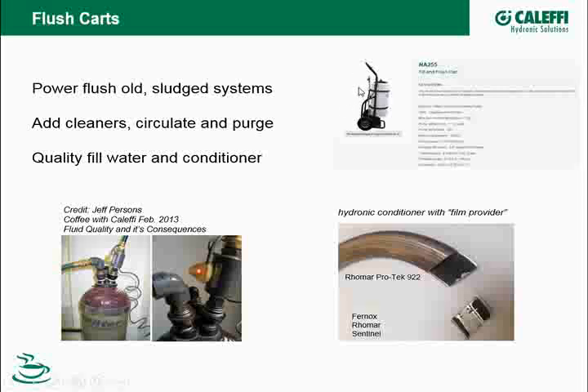Another tool that might be handy is one of these fill and flush carts. Now we build up a bunch of these for guys that were doing solar work. You just dump your glycol here and then you could pump it in there. But it can also be used for purging or cleaning systems. You could put a cleaning compound in here and just run it through there. It's got a pump that'll pump about 80 to 90 pounds pressure, so you can get a good scrubbing action going through the different loops and that.